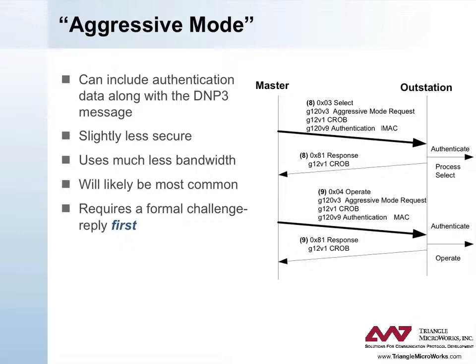The outstation authenticates this MAC and sends a normal select response. The operate sequence is similar, except that the DNP3 sequence number is incremented and an operate function code is used, as usual.